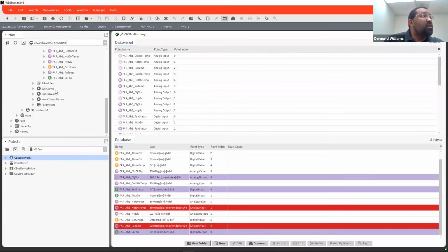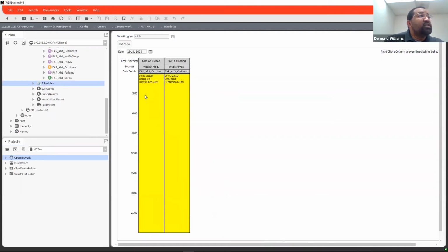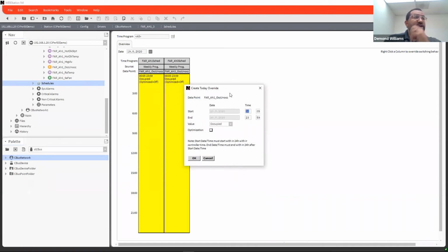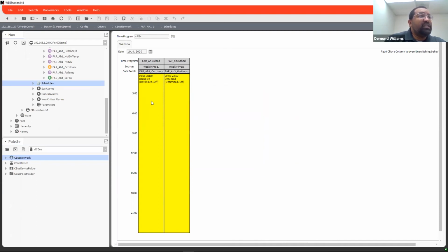Down here under schedules, here is the schedule. This schedule actually is an exact representation of what's actually in that controller. And this is exactly how it looks in the EBI system or XBSI system as well. So you right click on it, you can create overrides. Schedules can be imported up to Niagara schedules and push and pull that way. It's a little cumbersome to set up, or you can actually go in and delete these schedules and then basically just recreate them in the Niagara environment and let everything control that.